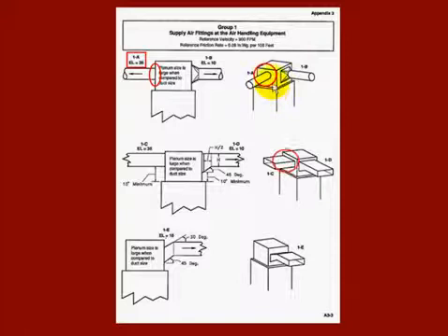All right. Can we improve this? Yeah, we can. There's a way to do that by creating wide mouth branches. This fitting, same situation, except it's not round, it's a rectangular duct. That's the side view of it. The fitting has the same equivalent length, 35 feet.